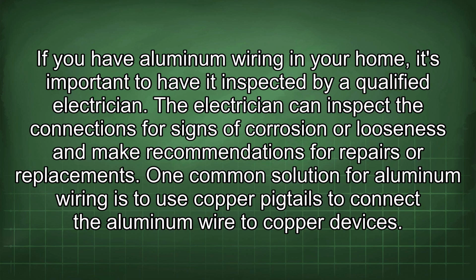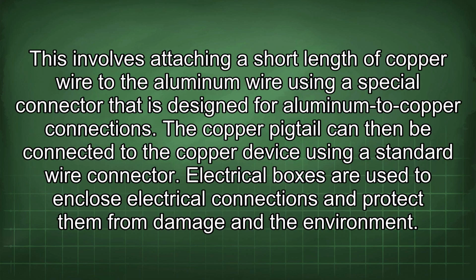One common solution for aluminum wiring is to use copper pigtails to connect the aluminum wire to copper devices. This involves attaching a short length of copper wire to the aluminum wire using a special connector that is designed for aluminum to copper connections. The copper pigtail can then be connected to the copper device using a standard wire connector.